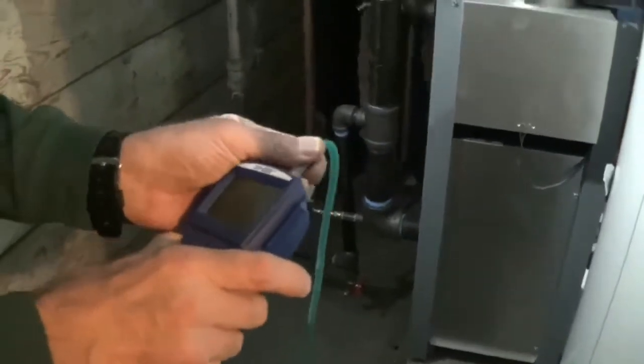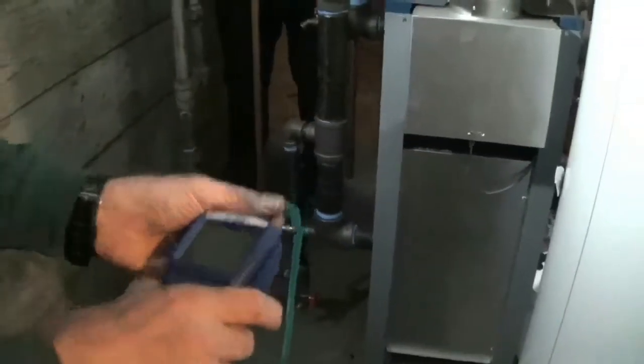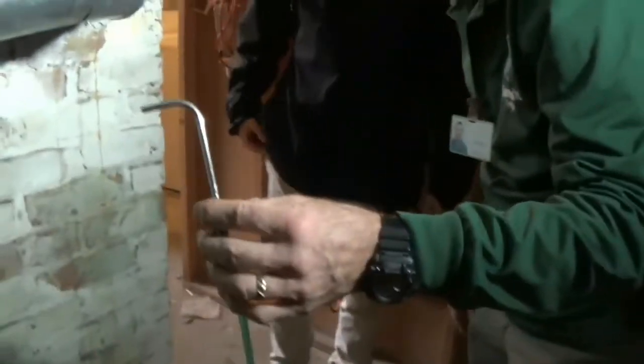So now, while it's running, we don't have much time. I'm back here because the hole is back here, and I am putting the hose to my manometer on the left side now because I'm measuring the pressure directly. I'm not measuring it with reference to anything else. And so remember, we calculated a minimum draft pressure. We wanted to get a negative number that is a more negative number than minus 1.825.